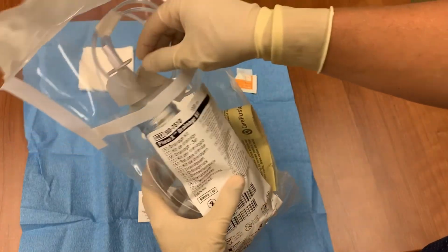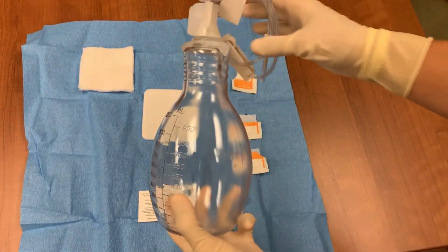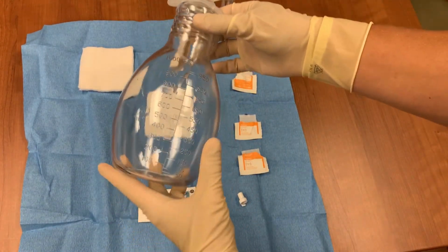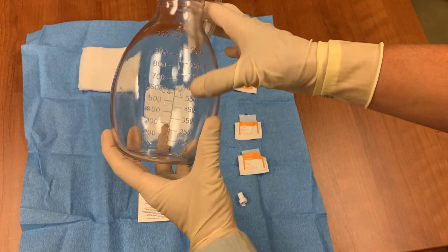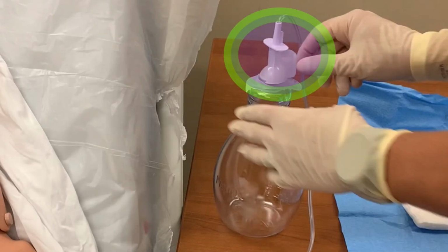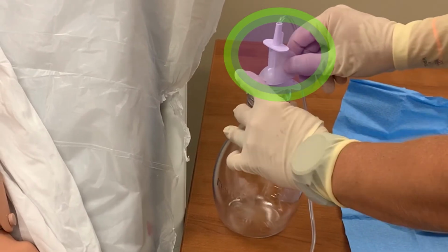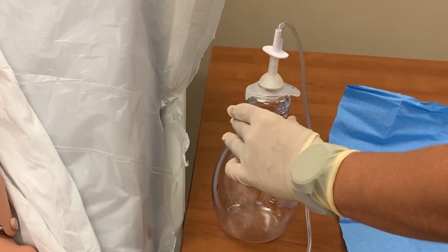Finally, we have the drainage bottle. The bottle can hold a maximum of 1,000 milliliters. It is vacuum sealed so that when activated, the negative pressure will actively pull fluid from the pleural space. There are markings on the side of the bottle to allow for accurate measurement of the drainage fluid. The bottle is capped with a T-plunger. While in the package, the T-plunger is protected from accidentally being pressed into the bottle by a plastic clamp. After taking the bottle from the package, the clamp can be removed.